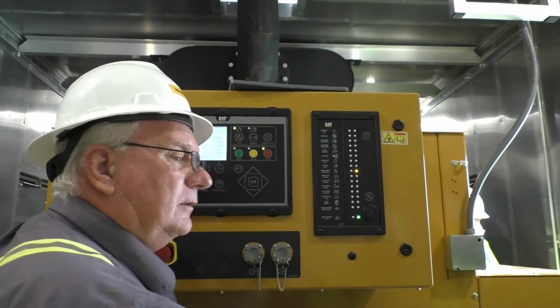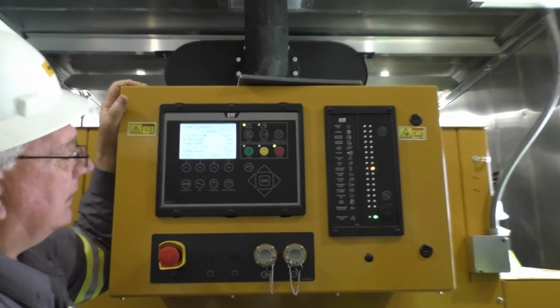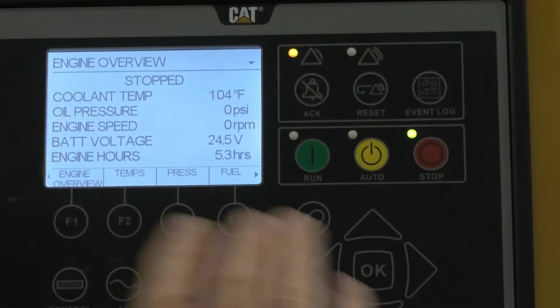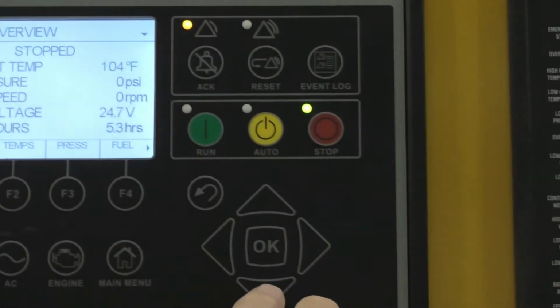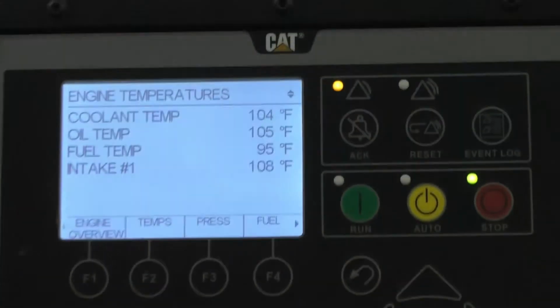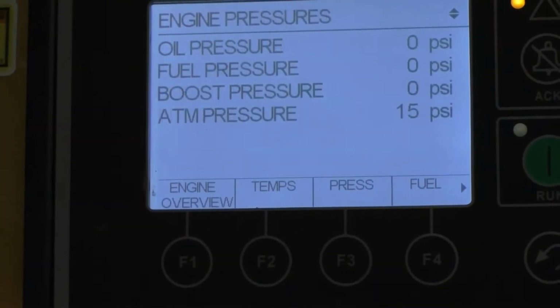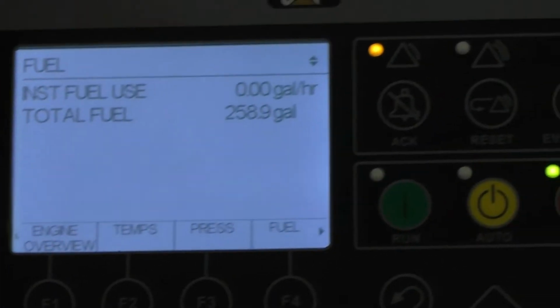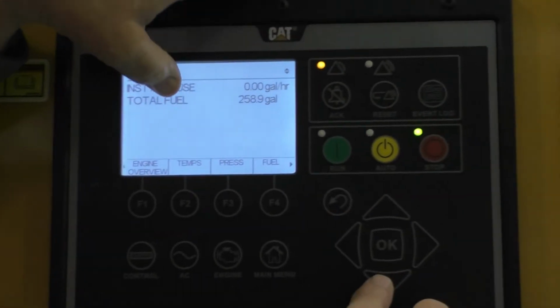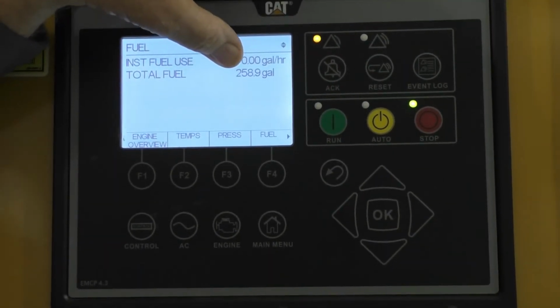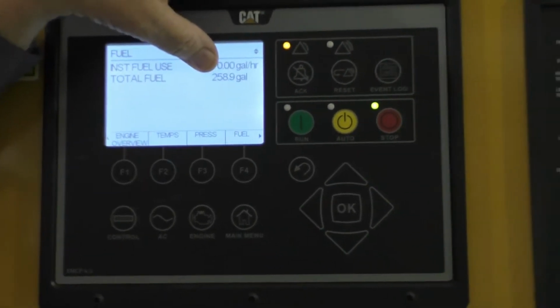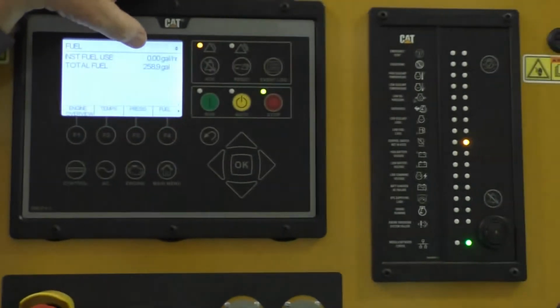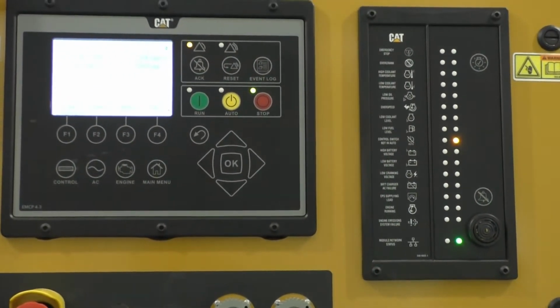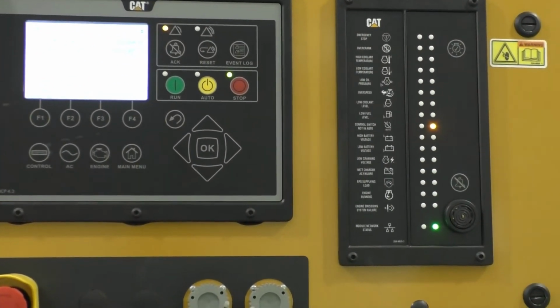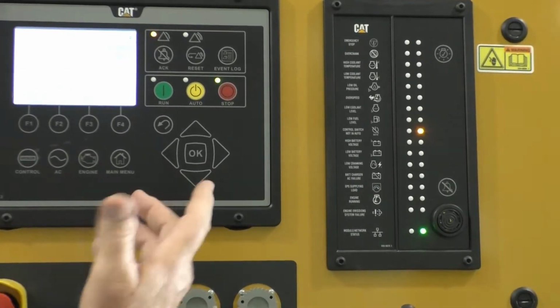Yeah, turn it on. That's off. Turn it on? Yeah. Glad we saw that. That'll make a big difference. But anyway, if you want to see other data, you can roll down in this and it'll give you all the temperatures, all the pressures. It'll tell you how much fuel you're burning. We've burned 258.9 gallons of fuel with the load test and all since it got on site. I can tell you at 100% load, it burns 58 gallons an hour. I doubt you're going to be at 100% load, but that's the max it should burn.